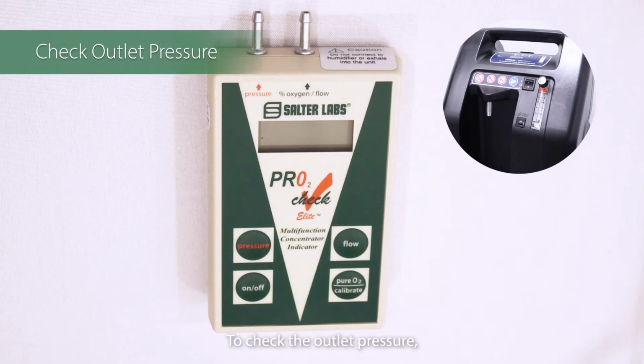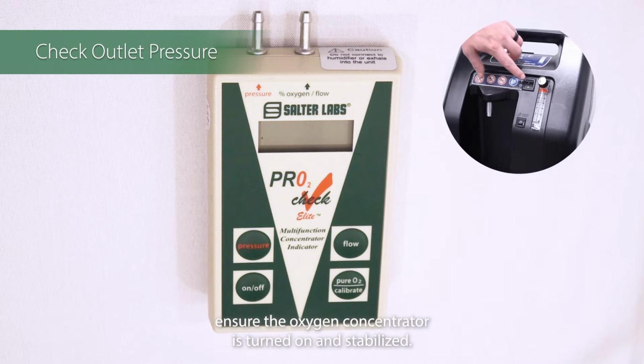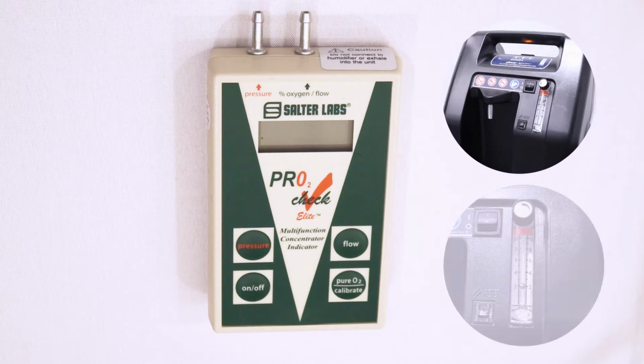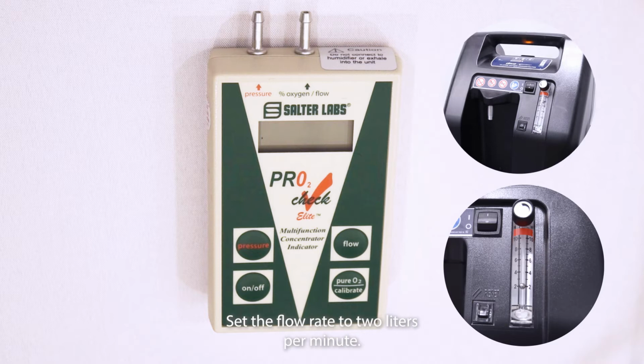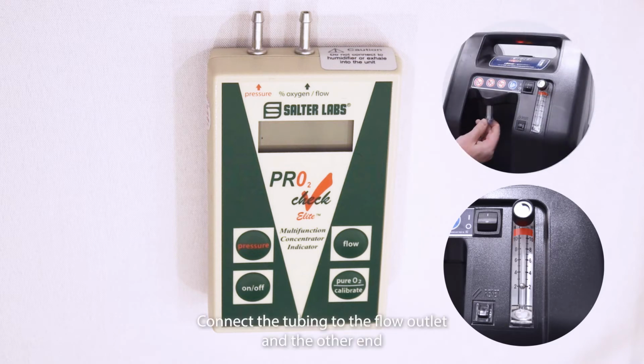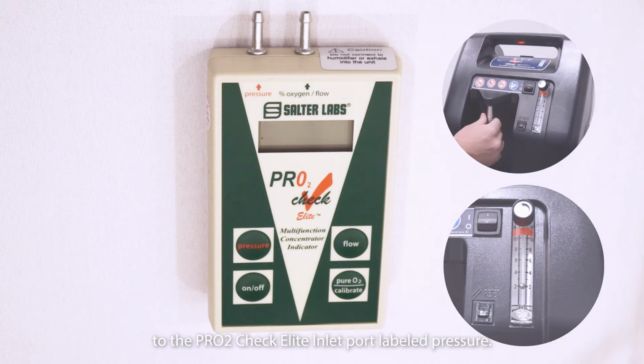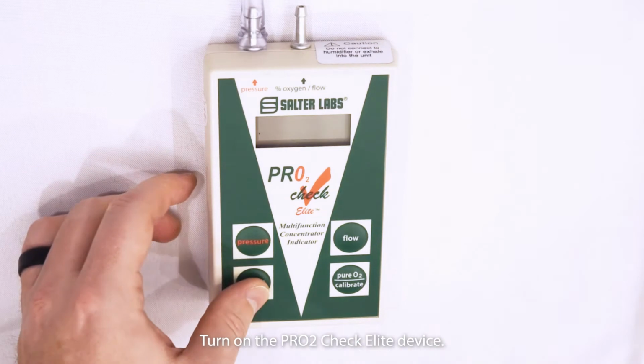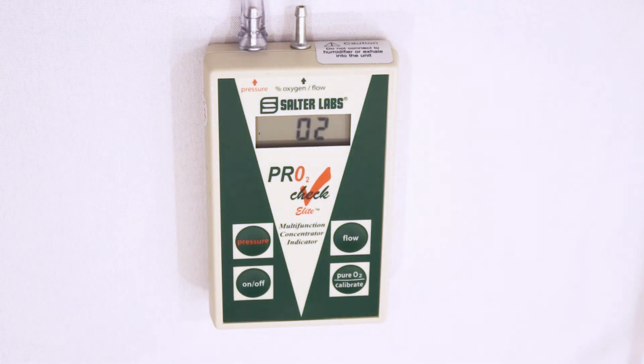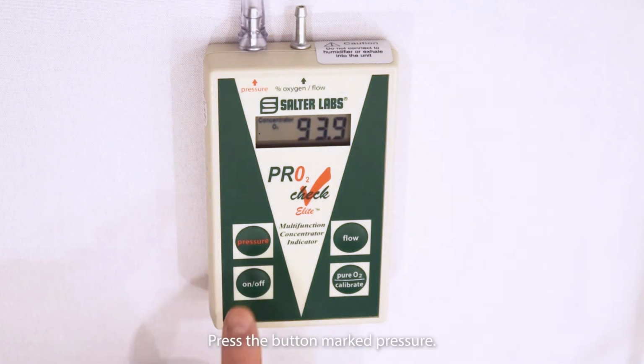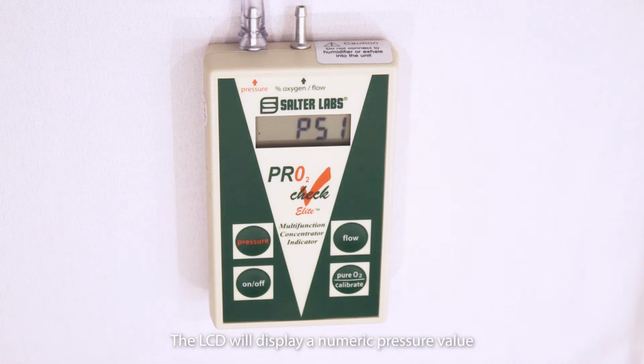To check the outlet pressure, ensure the oxygen concentrator is turned on and stabilized. Set the flow rate to 2 liters per minute. Connect the tubing to the flow outlet and the other end to the PRO2 Check Elite inlet port labeled Pressure. Turn on the PRO2 Check Elite device. Press the button marked Pressure. The LCD will display a numeric pressure value alternating between kilopascal or pounds per square inch.